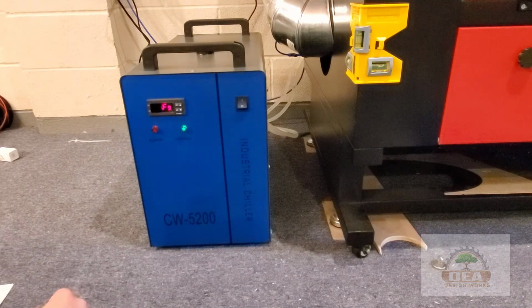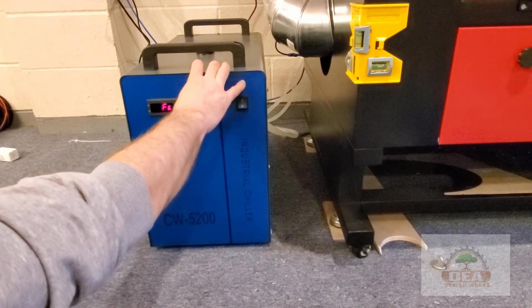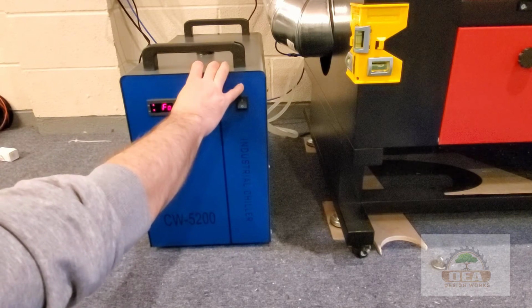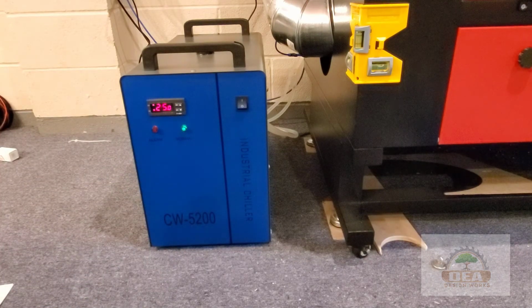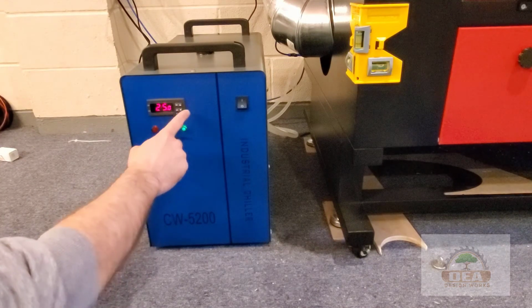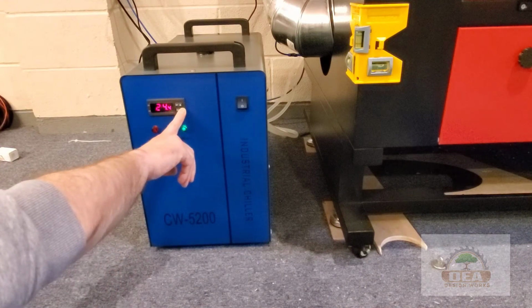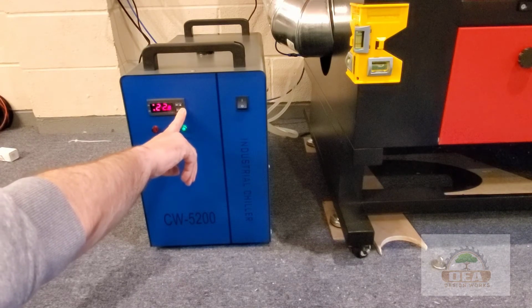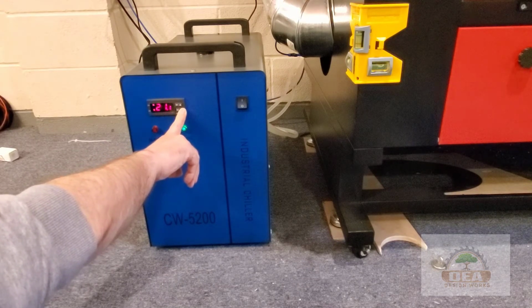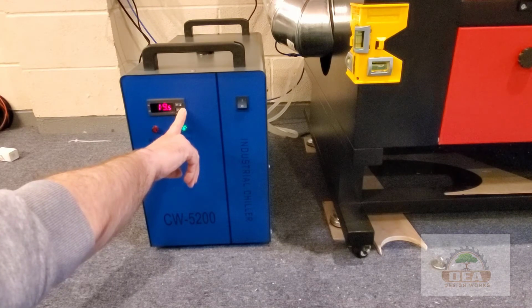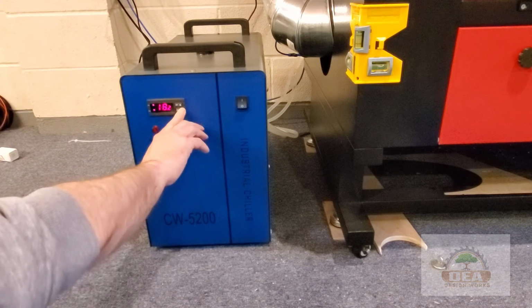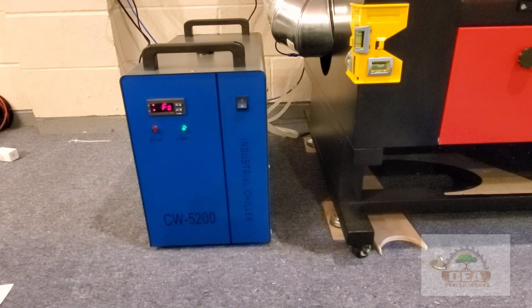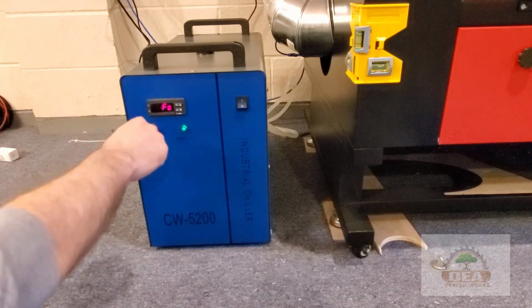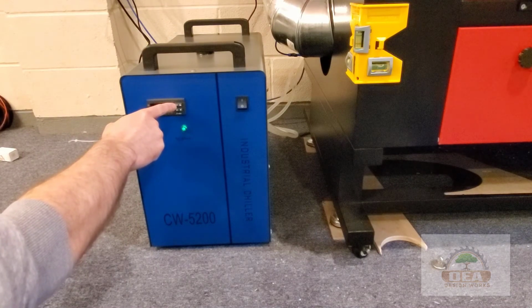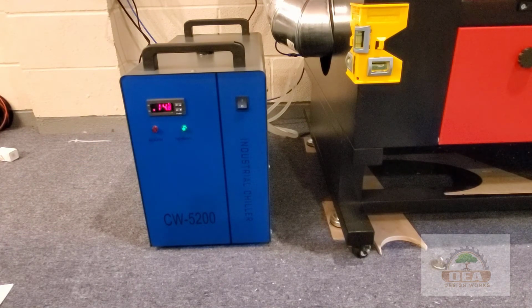And then I'm going to change this to F0. And I'm going to press set to enter that. And this is going to be what I want my constant water temperature basically to be at. So I want this one to be at 18 because I want to stay around 18, but I don't want it to go any lower than 15, which is what we just changed here. So let's see here. So we're going to continue to hold that, get it down to 18. We'll press set there. And now it goes back to the F0. So if I press the RST button, it should save those settings, and now we should be good to go.